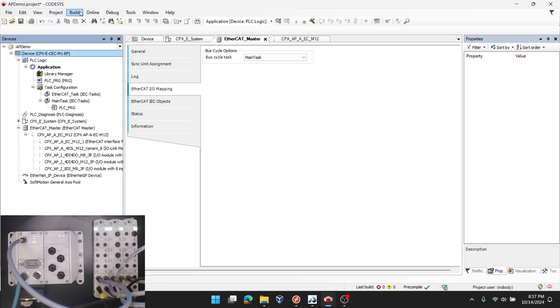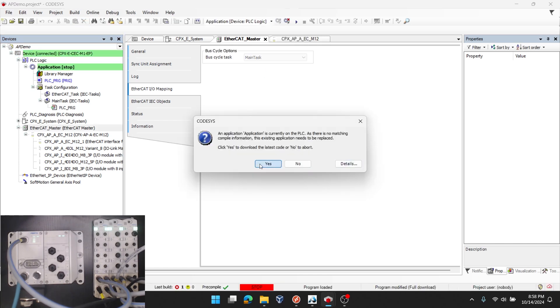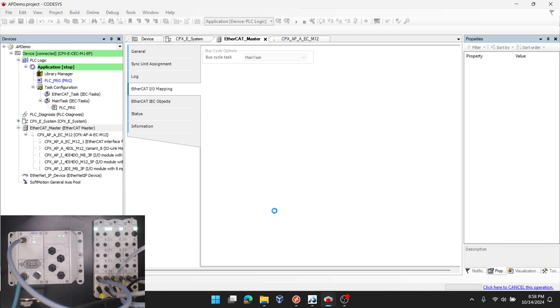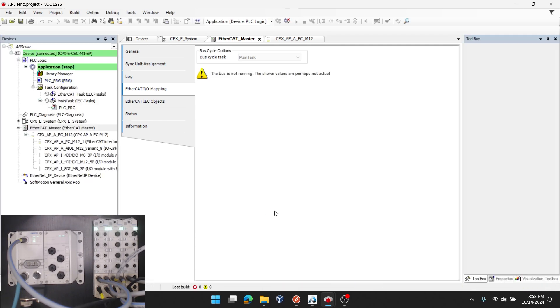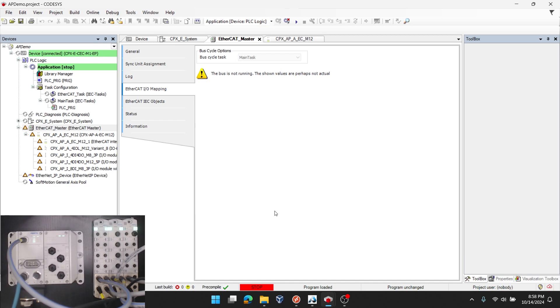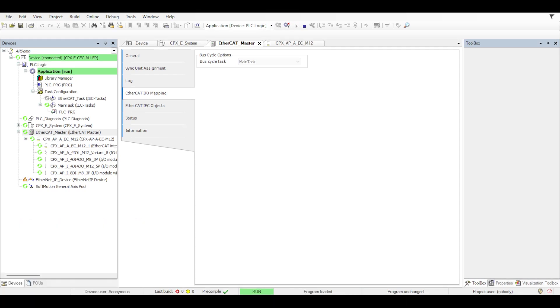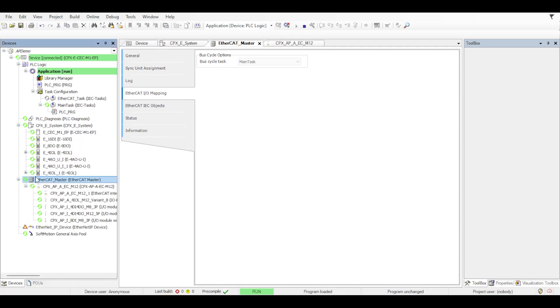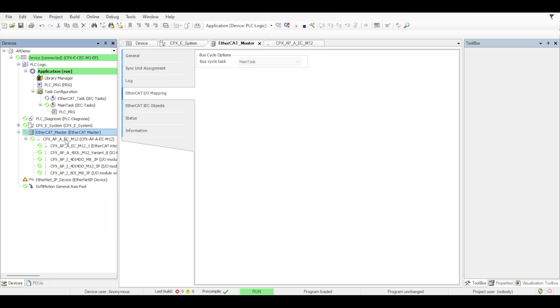Now go back to the PLC level, build, and then I'll log in with the device. When prompted to download the latest application code, I click yes. And then I'll start the PLC by pressing the start button or F5. Notice if I expand the CPXE system and the EtherCAT master system that we have the green recycle icon next to each and every slice. That means everything's being detected and it's updating at the frequency set up in the task configuration.